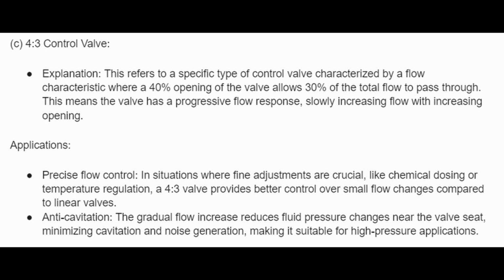Applications. Precise flow control. In situations where fine adjustments are crucial, like chemical dosing or temperature regulation, a 4-to-3 valve provides better control over small flow changes compared to linear valves. Anti-cavitation. The gradual flow increase reduces fluid pressure changes near the valve seat, minimizing cavitation and noise generation, making it suitable for high pressure applications.